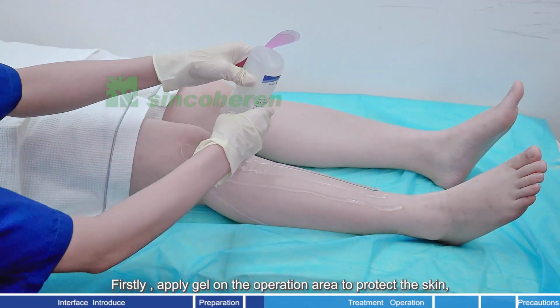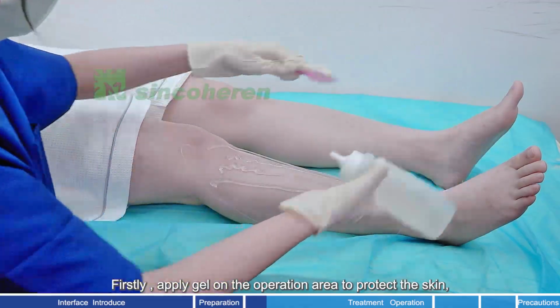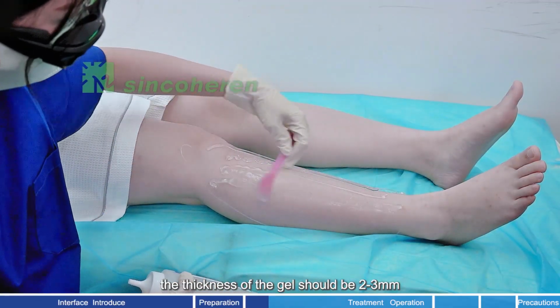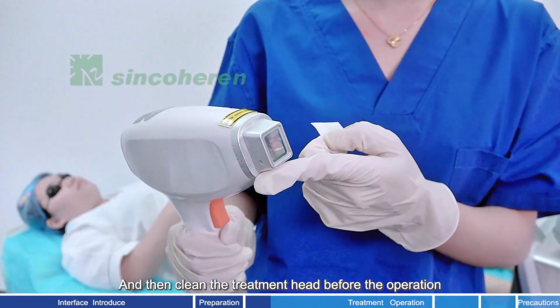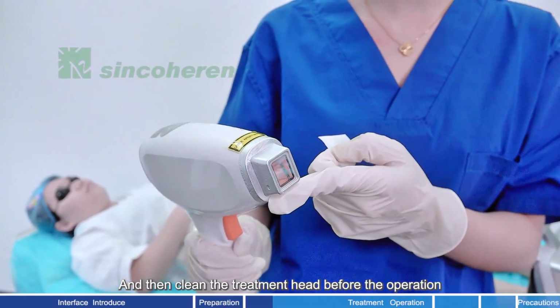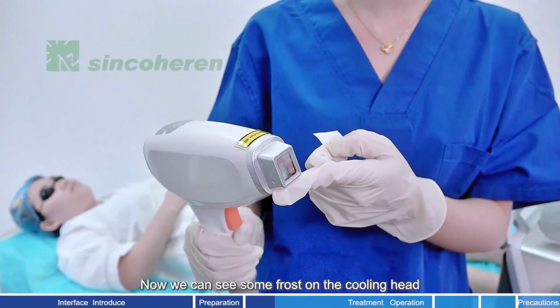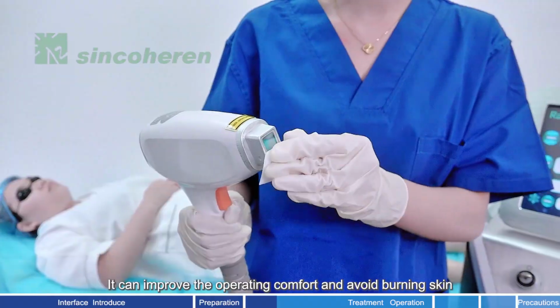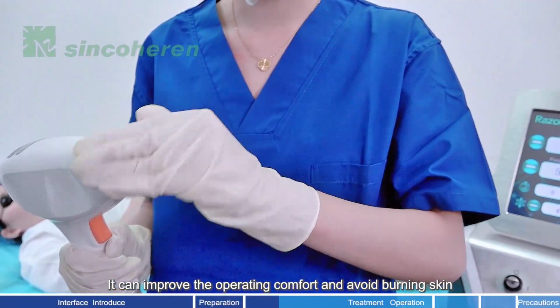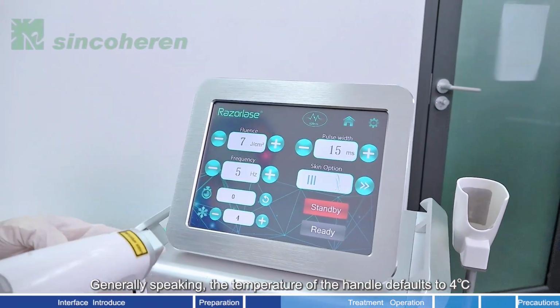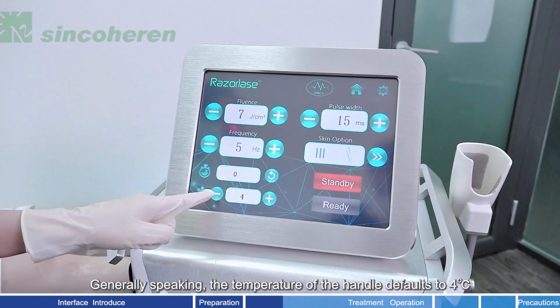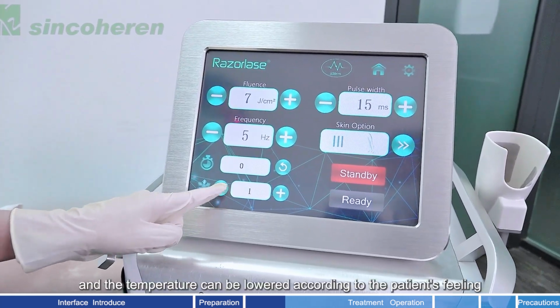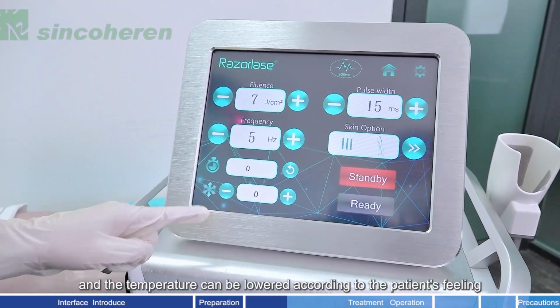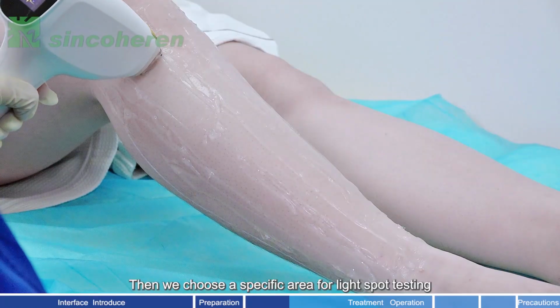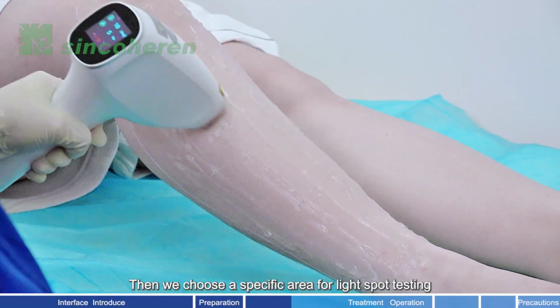Firstly, apply gel on the operation area to protect the skin. The thickness of the gel should be 2-3 mm. And then clean the treatment head before the operation. Now we can see some frost on the cooling head. It can improve the operating comfort, and avoid burning skin. Generally speaking, the temperature of the handle defaults to 4 degrees Celsius. And the temperature can be lowered according to the patient's feeling. Then we choose a specific area for light spot testing.